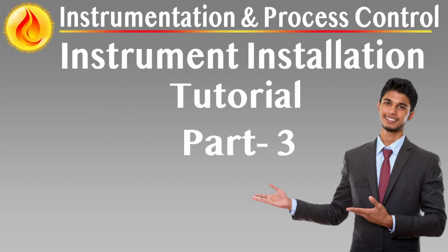Calibration design, adapting to plug-free installations. In systems where diaphragm seals are used to prevent plugging, equalizing lines are typically avoided as they present the same clogging risks as traditional impulse tubing. Instead, these systems rely on vent ports, flushing rings, or purge connections for calibration and maintenance activities.